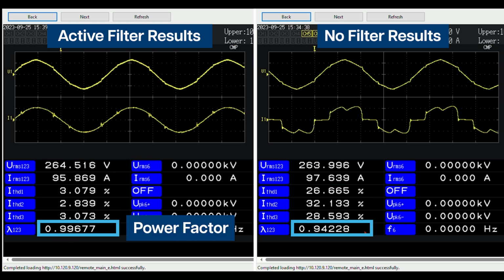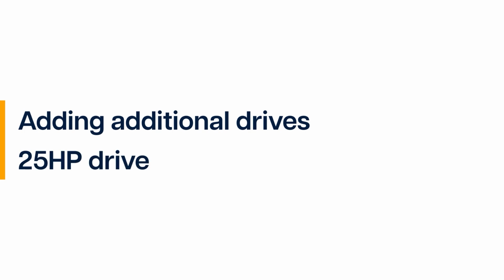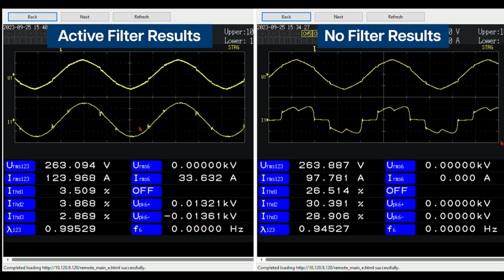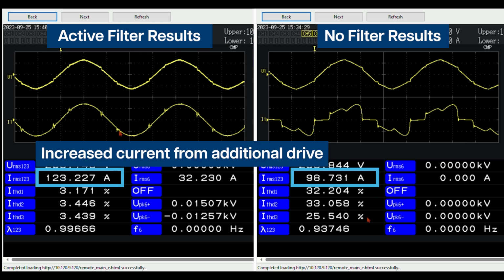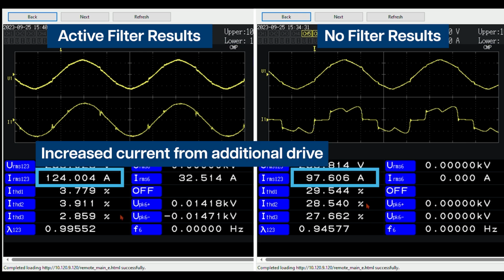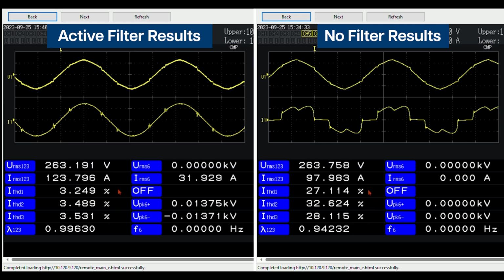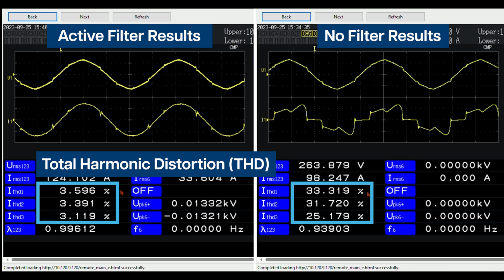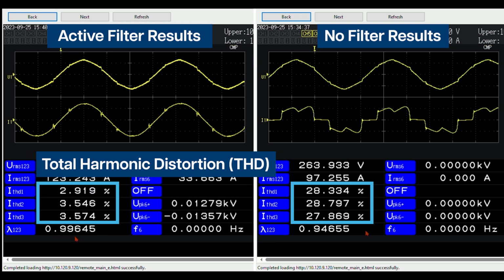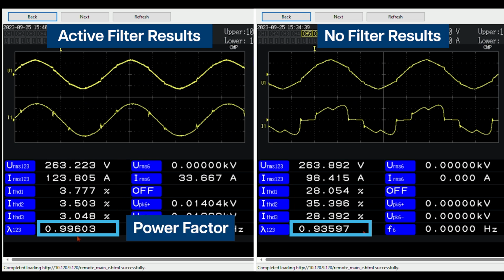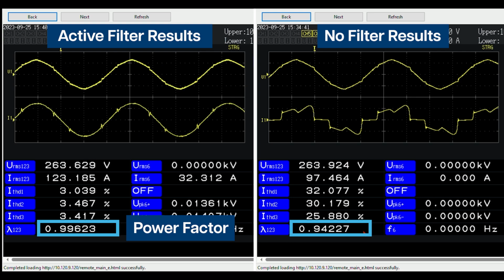It is perfectly suited for systems with fluctuating loads. The active harmonic filter will dynamically adjust in real time, effectively keeping harmonic distortion significantly under 5% and enhancing the power factor to nearly perfect levels.